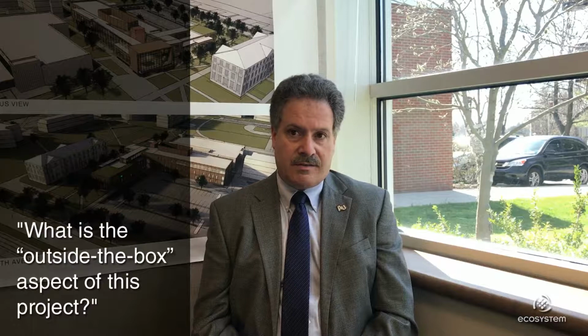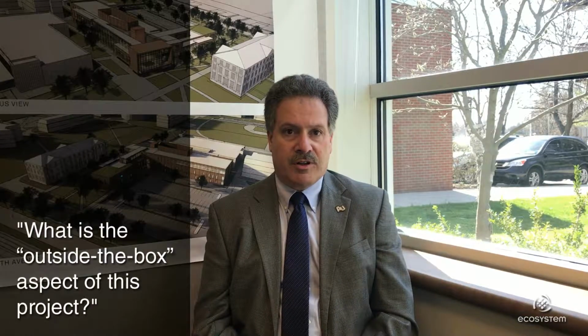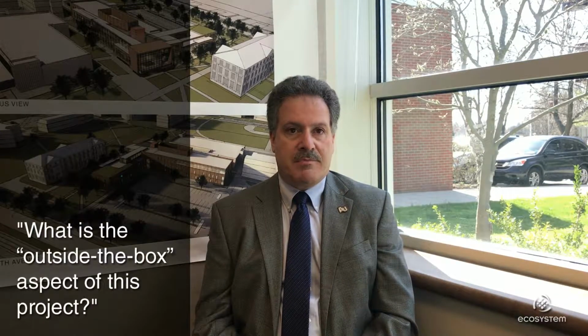One of the other problems that added complexity to this project was that when we initially looked at our boiler room, it seemed simple on paper. We had plenty of room to work. But when we started placing equipment on the floor plan, we quickly realized we weren't going to be able to put everything on the floor. So we had to get creative, and Ecosystems came up with a method of building a mezzanine above working height, so we could put a lot of the heat exchangers and air handlers for the cogen up there, keeping adequate space on the floor.